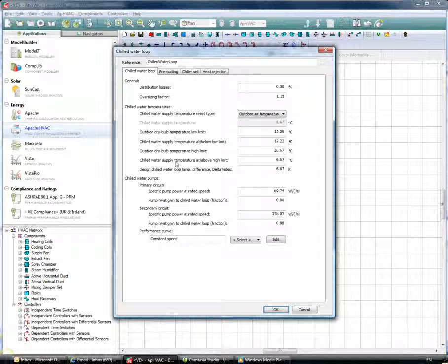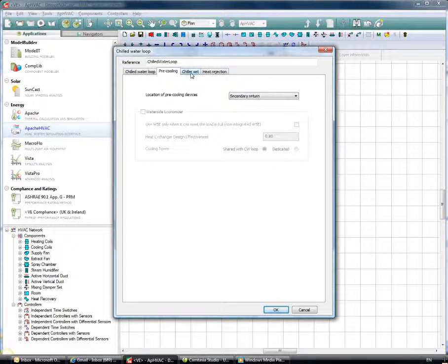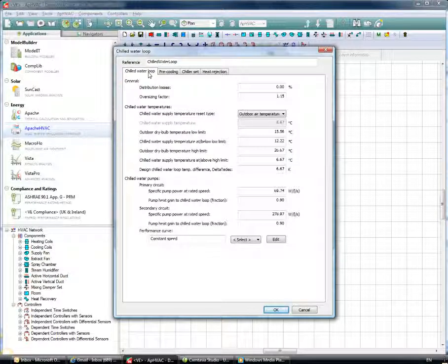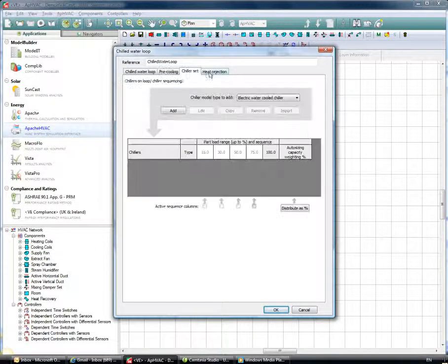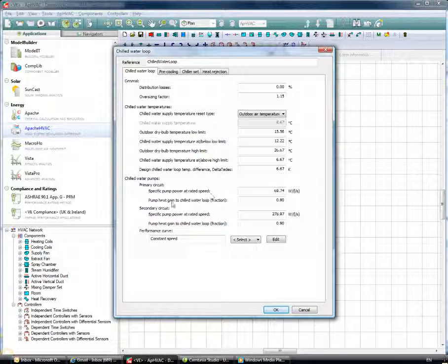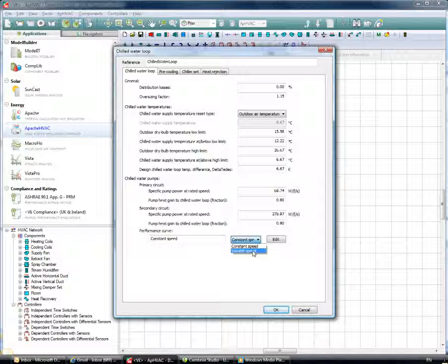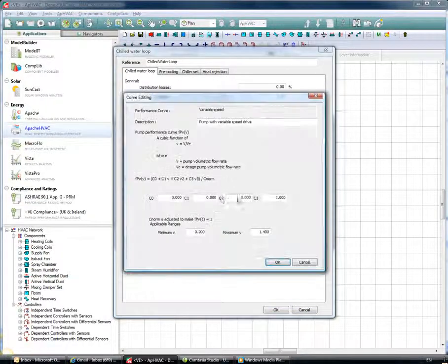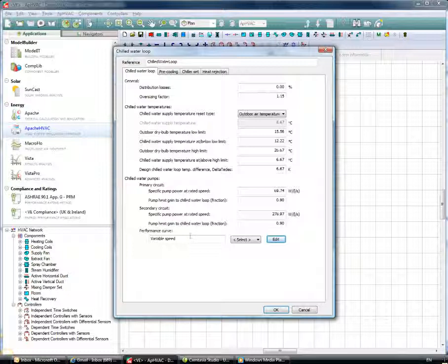Clicking the Add button for the chilled water loops, I can see the chilled water loop with multiple tabs to model the water side and the generator in detail. In the Chilled Water Loop tab, we can input items such as chilled water pumps — a primary circuit and secondary circuit pump — with pump power at rated speed and pump heat gain to the chilled water loop as a fraction. We'll change the pump curve from constant speed to variable speed.